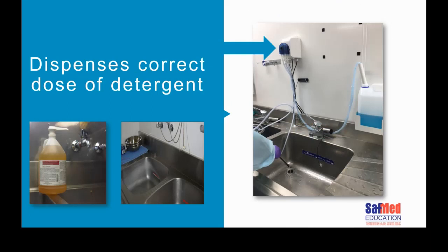Another important concept is that we dose the correct amount of detergent so that we have the correct water and detergent dilution. In order to achieve this, the first thing, of course, is that we tend to mark our sinks. The reason we mark our sinks is that we understand exactly how much water is in the sink so that we know, based on the manufacturer's instructions, what volume of detergent to add to that mix. Again, at the site in the UK, you can see not a very pretty looking contraption, but a contraption that dosed the specific amount of detergent to make sure that the detergent mix was correct.